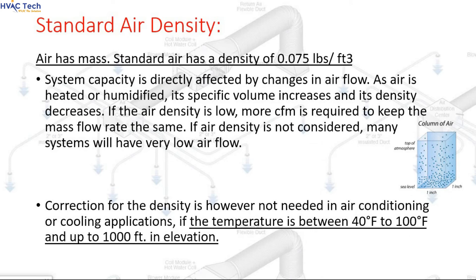Standard air density: air has mass. Standard air has a density of 0.075 lbs/ft³. System capacity is directly affected by changes in airflow. As air is heated or humidified, its specific volume increases and its density decreases. If the air density is low, more CFM is required to keep the mass flow rate the same. If air density is not considered, many systems will have very low airflow.